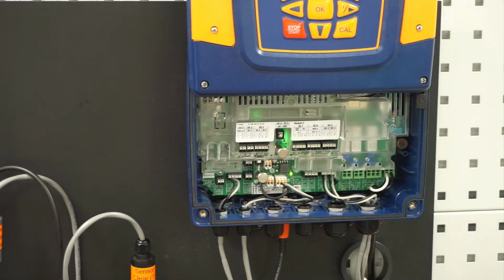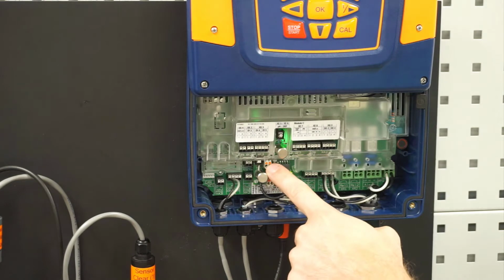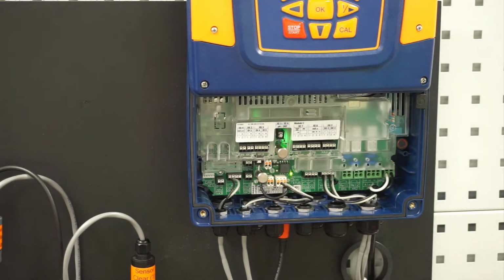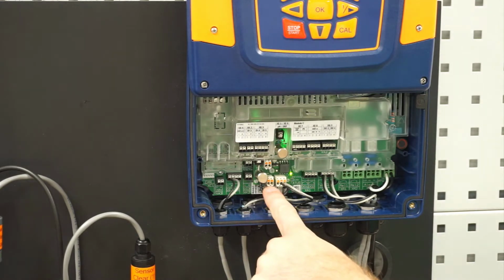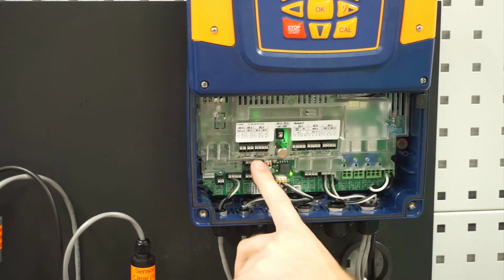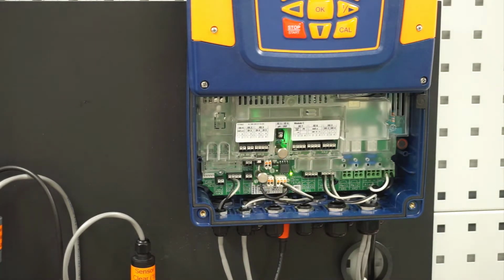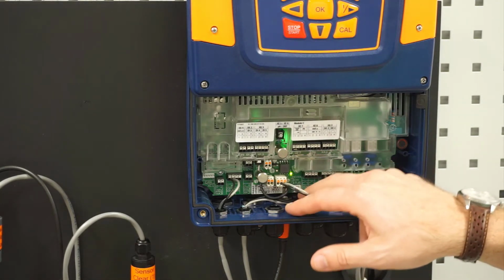That is a liquid potential. So if there are any disturbances in the water, stray voltage, if there are a lot of big motors or drives in the actual area where this controller is installed, that millivolt signal may be interfered with by those components. We can actually take this wire out and run a wire from there and ground it on the water pipe, and that would get rid of some of that interference for us. Also, we're not using it here, but we also have a place to put a temperature sensor, all on that half of the card.